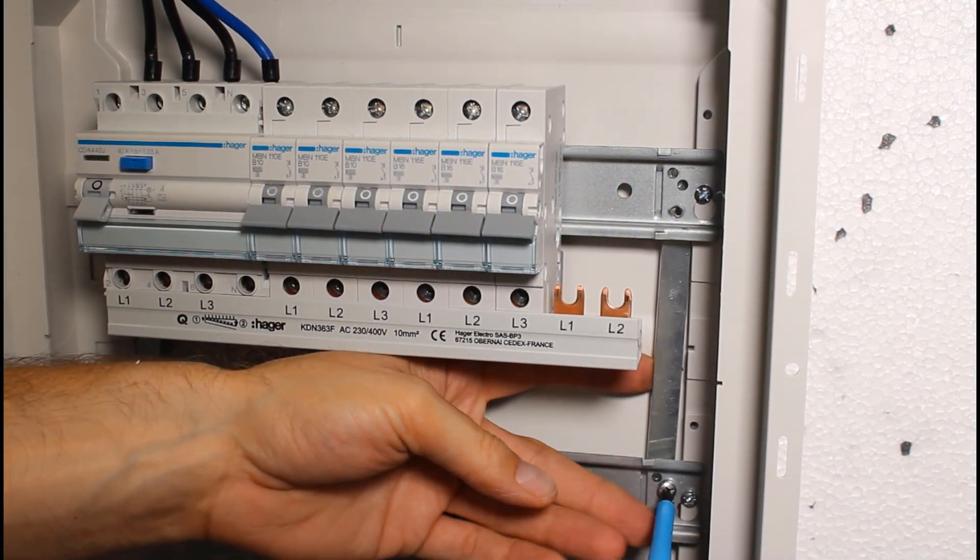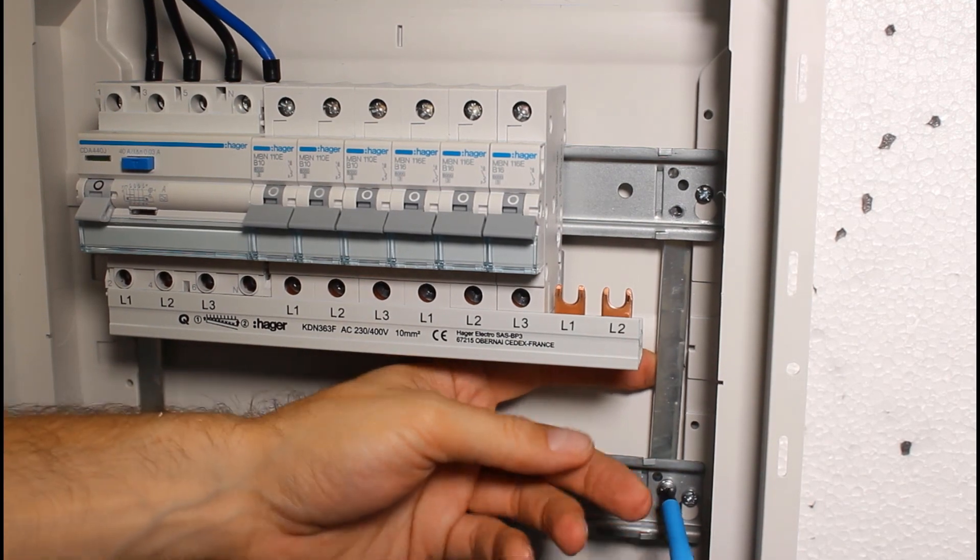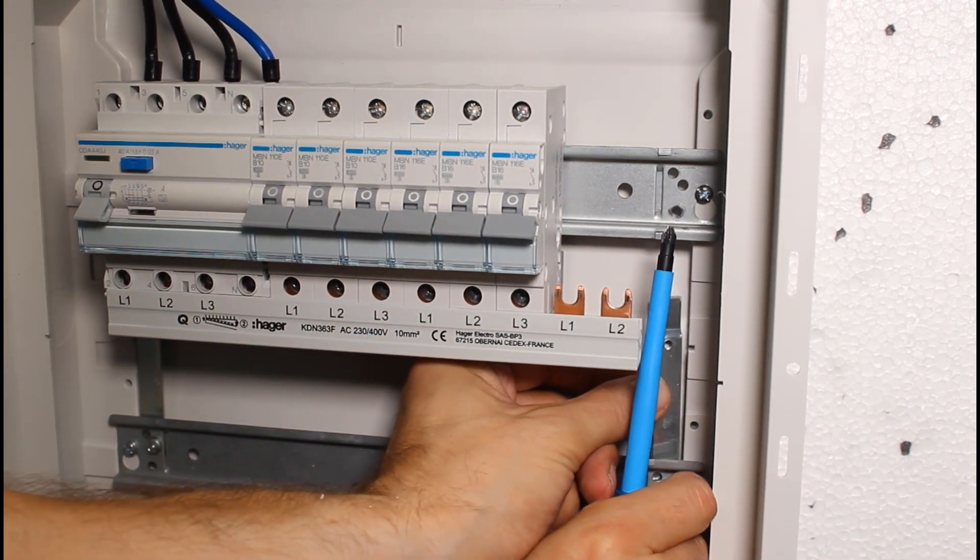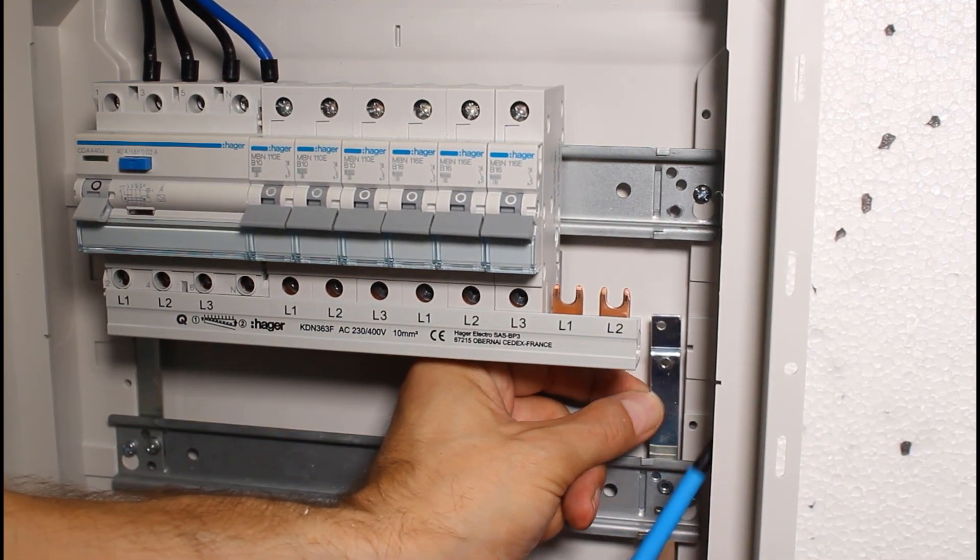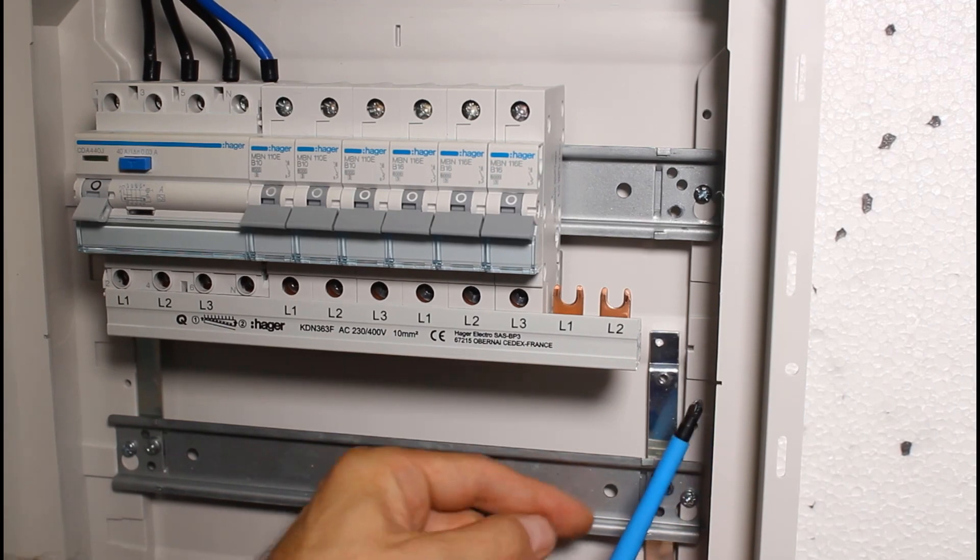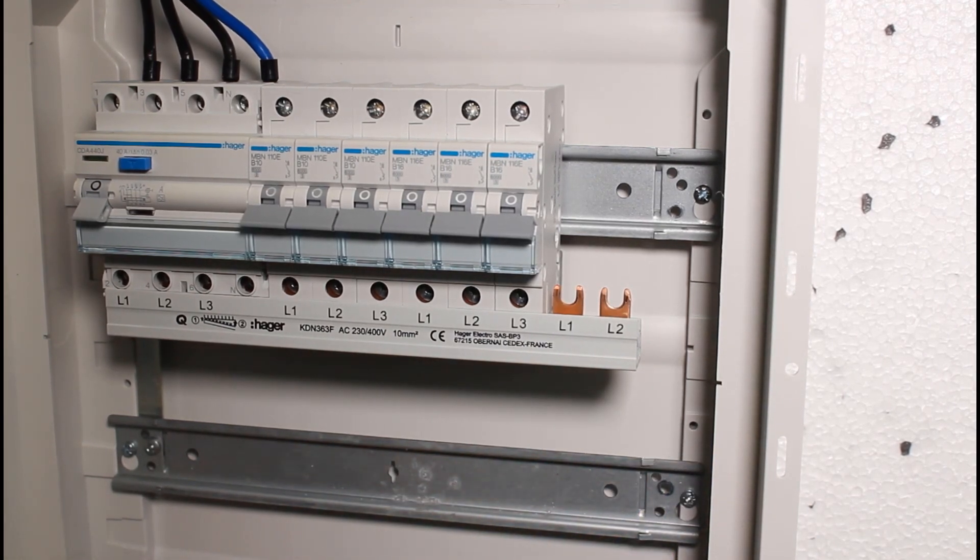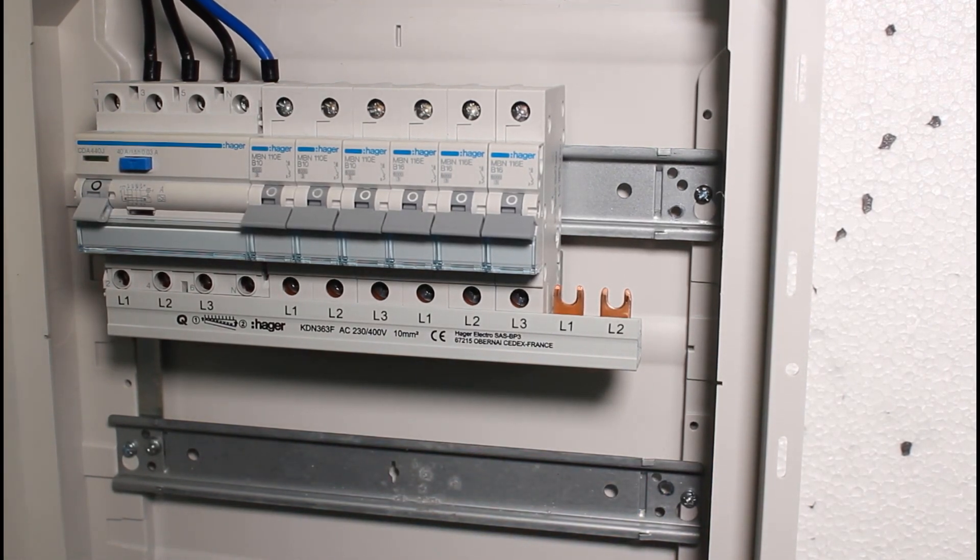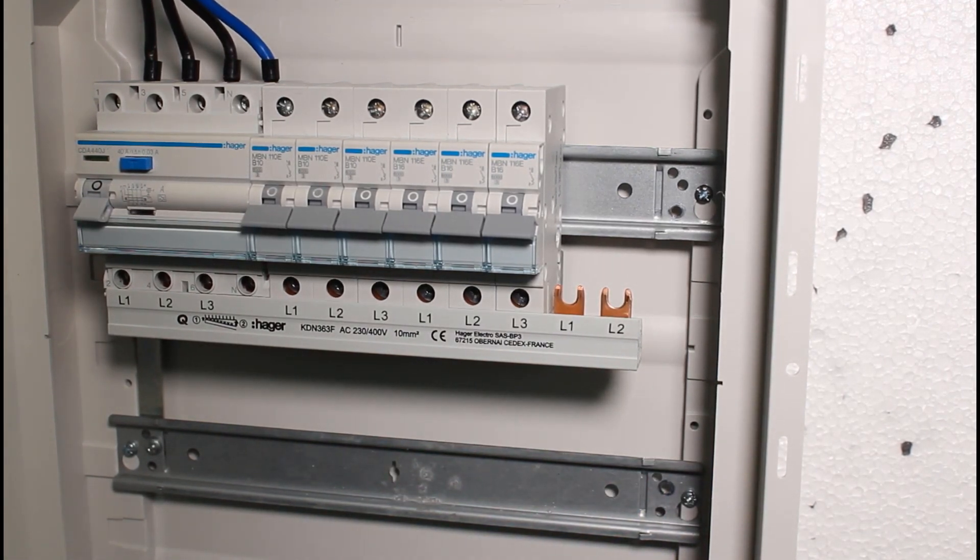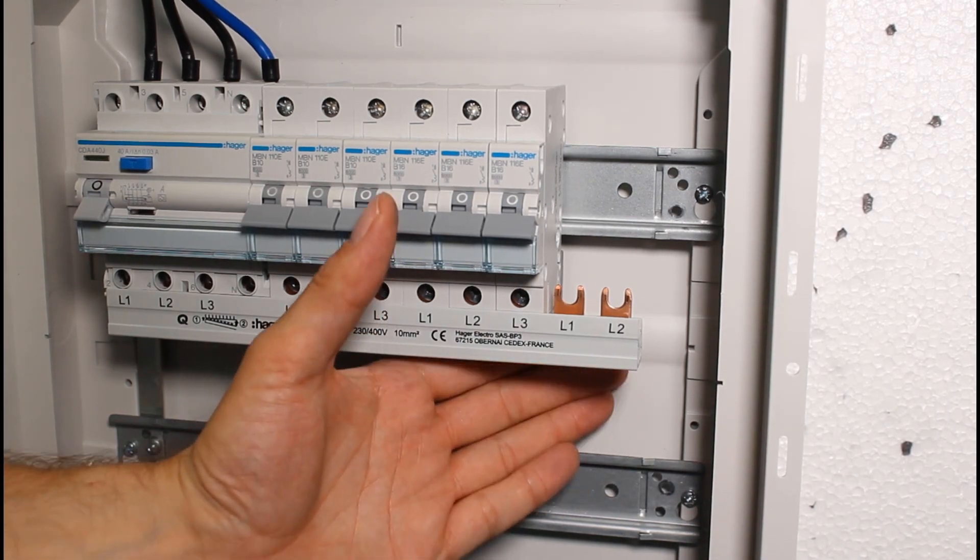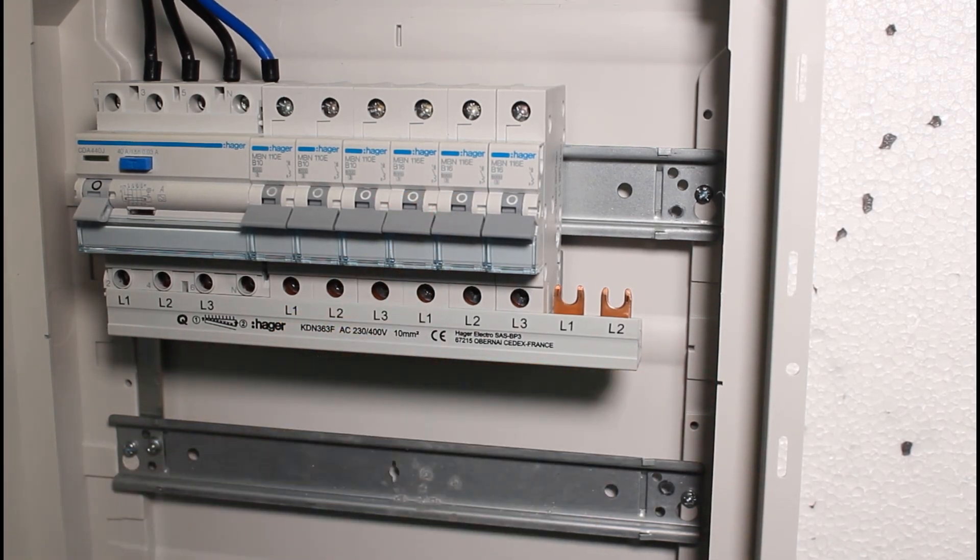Vertical connecting sections fixed with screws provide equipotential bonding between individual mounting rails. If one of the rails is used as a common protective bar, it should be separated from the other rails for safety reasons.